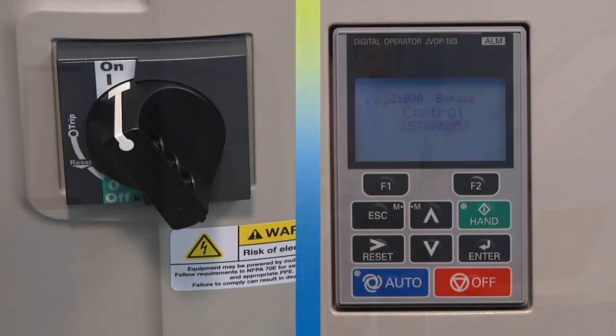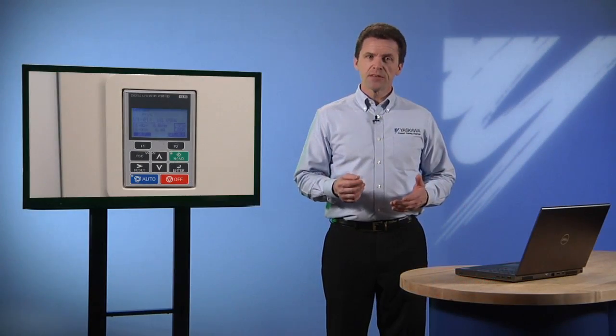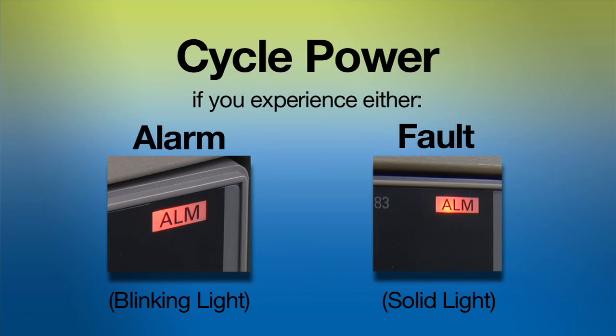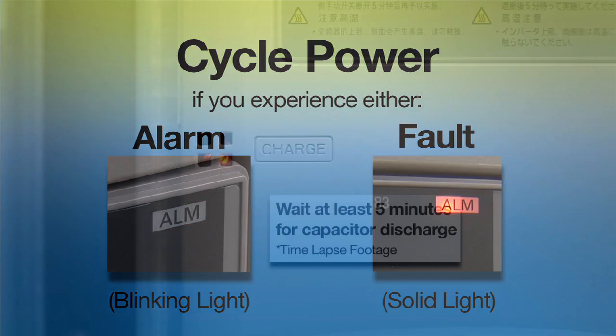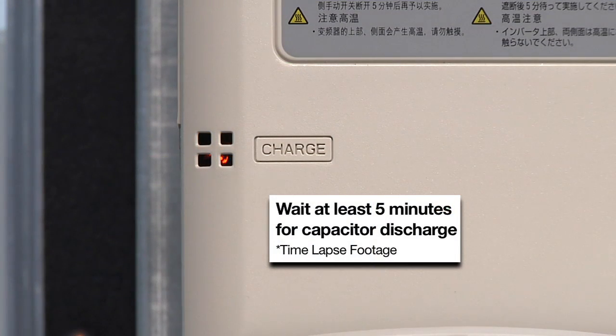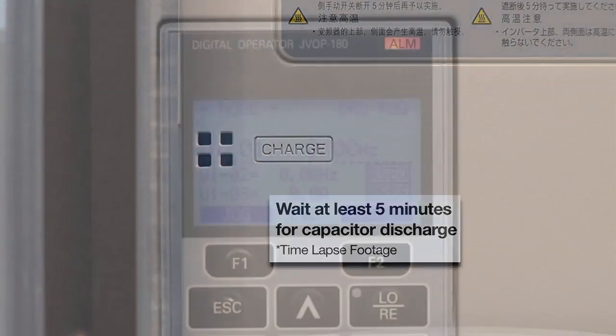When you power up after flashing, make sure the system indicates no alarms or faults. If an alarm or fault arises, cycle power to the drive once again. Cycling power too quickly can often cause an alarm or a fault. So be sure to leave the drive powered off until the charge light is completely extinguished. If you aren't certain, wait a while longer.